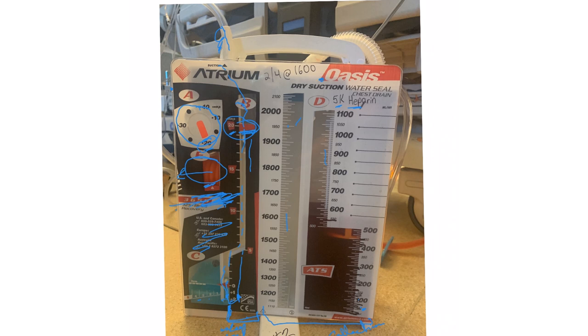This is a type of chest drain — 5K heparin — designed to be used for cell saver, which means they collect the blood, put it in the cell saver machine, and transfuse it back to the same patient. So the patient gets their own blood transfusion — something we'll talk about later. This is the collection right here, this is the water seal hidden by the black marking, and this is the negative pressure suction. The management of this is mainly handled by nurses, but we'll talk about what we need to look for when taking care of patients with a chest tube in the next video.